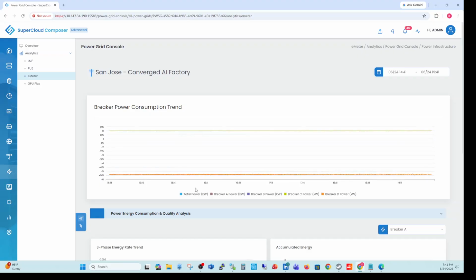So it came back here with our consumption trend. We're talking total power, breaker power. We have different C clamps on various breakers collecting different things. You may want to think about putting breakers in a transformer, or look at breakers related to consumption of a cooling tower, or breakers associated with power used by an in-rack CDU or in-row CDU, so you can get visibility into various power sources you're drawing and better understand how well you're consuming and optimizing power in your converged AI factory.